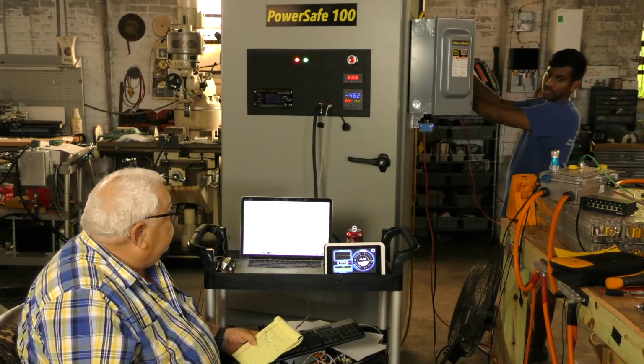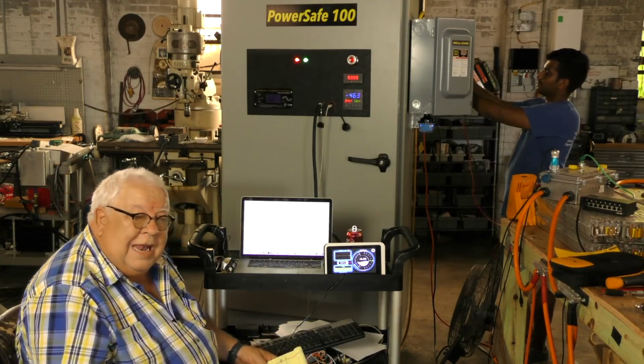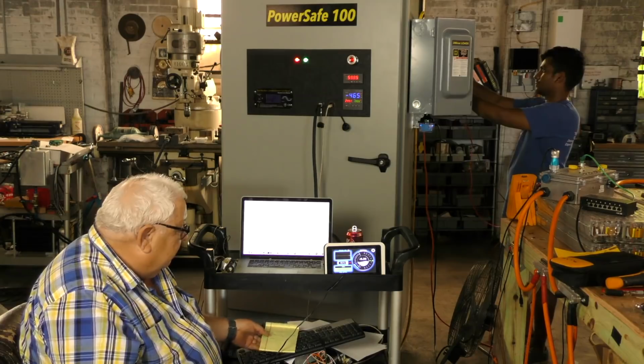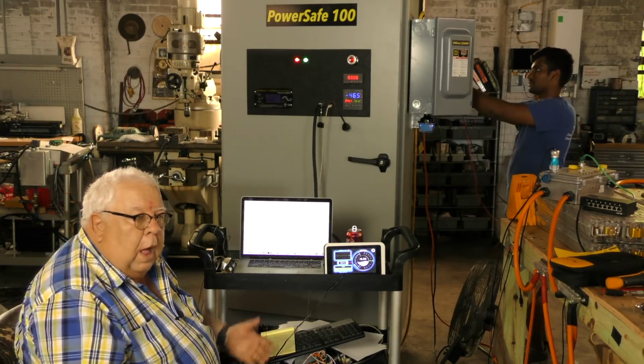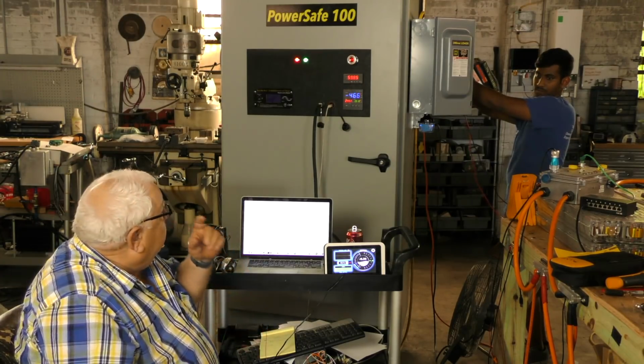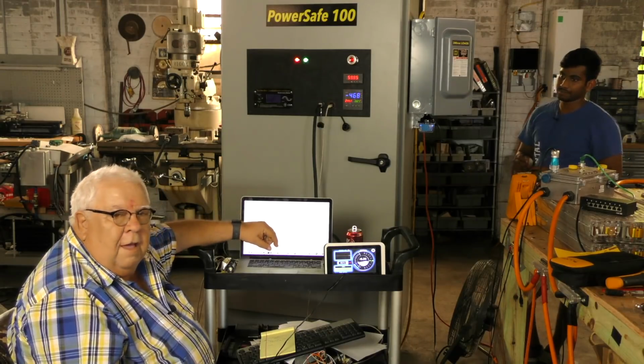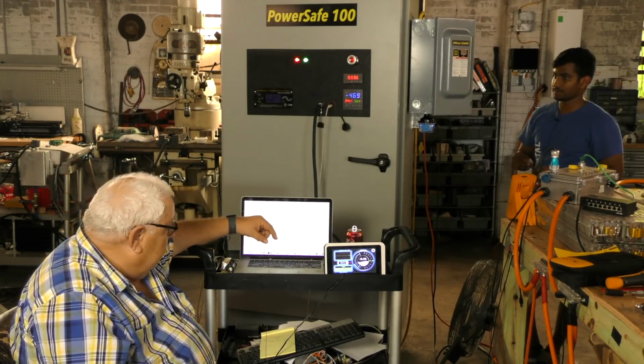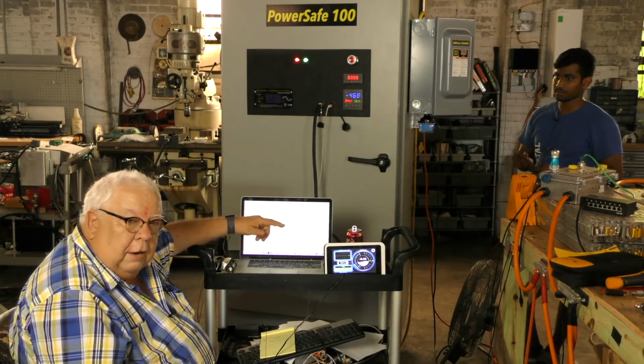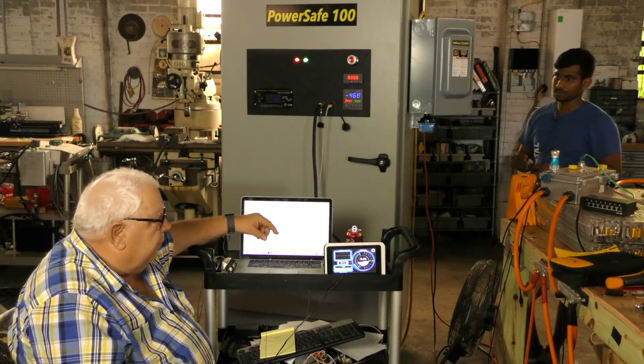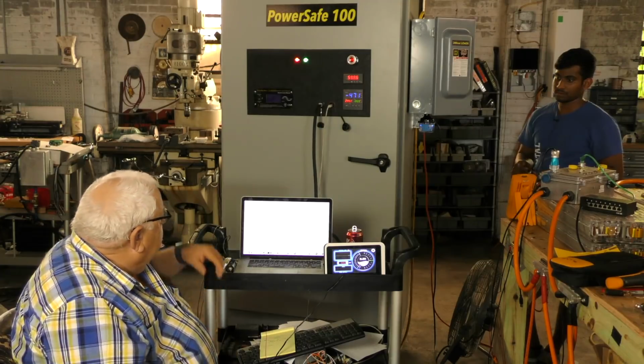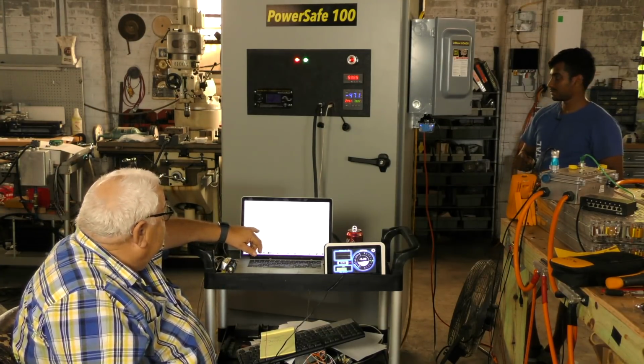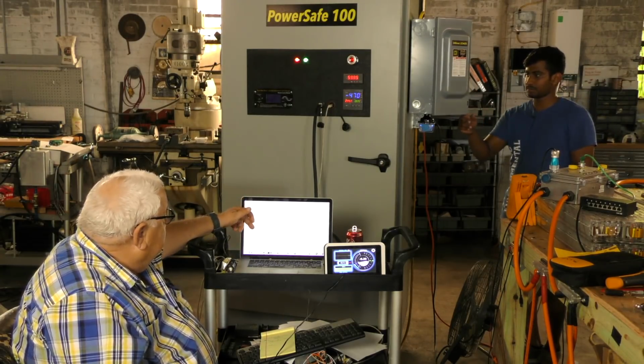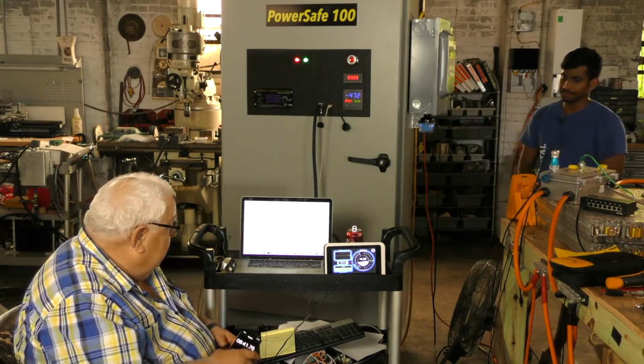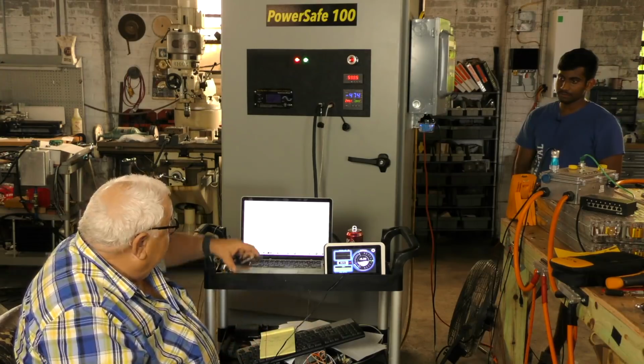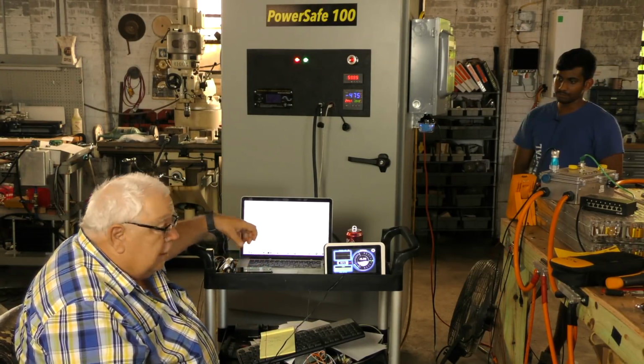What's our voltage now, Danu? 245.9. And what that is, all grid-tied systems try to lock into phase and frequency with the grid voltage, and we're at 59.86 hertz on our power safe, and they bump the voltage just a little bit - they put out a little higher voltage than whatever the grid is doing, so that they act as the current source. These have come up right at 5 minutes and 12 seconds, and we are indeed charging using our IQ7X.